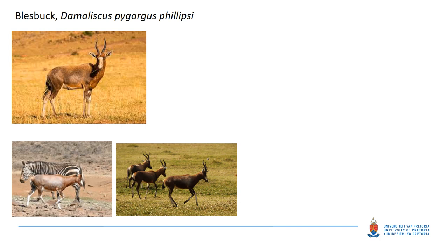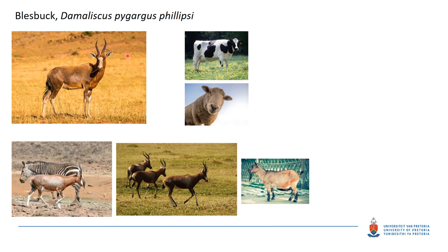For the first example, we're going to look at the blesbuck, a medium-sized African antelope. Let's say you are handed an EDTA sample from a blesbuck and you're standing in front of your hematology analyzer. What species setting are you going to choose? In terms of domestic ruminants, you have the choice of a cow, a sheep, or a goat. You might think a blesbuck looks similar to a little goat, so you'd go for the goat setting.